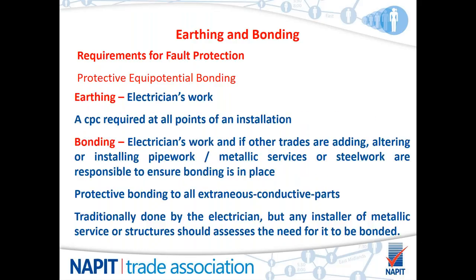Okay, so responsibility for earthing and bonding. With regards to earthing, it's an electrician's work, and a CPC is required at all points of an installation. Bonding, again, will be electrician's work, and if other trades are adding, altering, or installing pipework, or additional metallic services, or steelwork, they are responsible to ensure the bonding is in place.